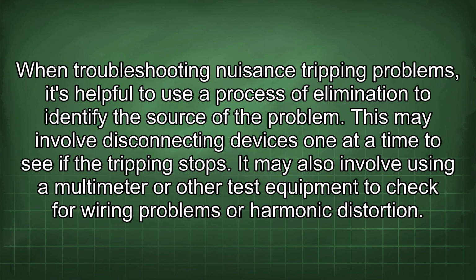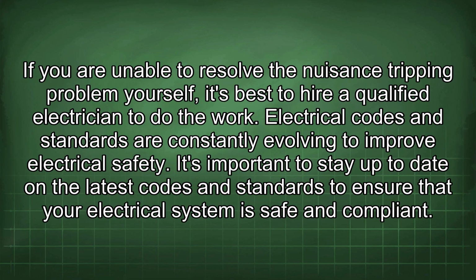When troubleshooting nuisance tripping problems, it's helpful to use a process of elimination to identify the source of the problem. This may involve disconnecting devices one at a time to see if the tripping stops. It may also involve using a multimeter or other test equipment to check for wiring problems or harmonic distortion. If you are unable to resolve the nuisance tripping problem yourself, it's best to hire a qualified electrician to do the work. Electrical codes and standards are constantly evolving to improve electrical safety.